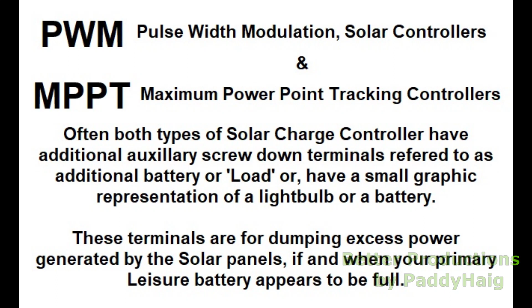Extra remote switch screw-down terminals are often just for a solar controller on-off switch extension. These might be wired to a lithium-ion LiFePO4 battery's BMS device, which relays to the solar controller that the battery is full or there's a problem, stopping the controller from passing more electricity by effectively isolating the solar panels from the controller.